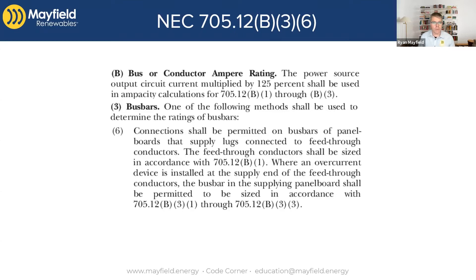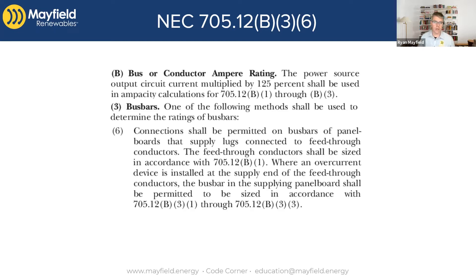In 2020, we have this language — connections on the bus bars that supply lugs connected to feed-through conductors. We'll go through what the scenarios are with a couple of images. The big thing to recognize is that it gets referenced back to 705.12 B1, which talks about connections to feeders. If we put in an overcurrent device to protect at the feed-through lugs, the downstream conductors and panels, we're actually able to utilize the 120% rule in 705.12 B3.2.